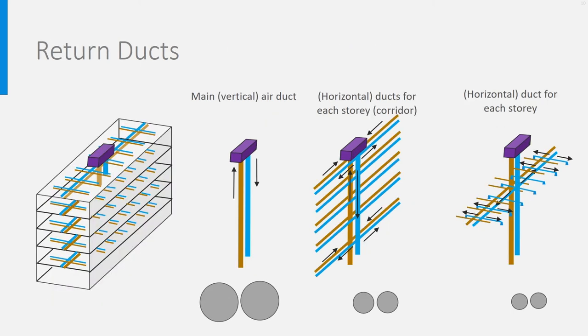This was all for the supply ducts. But when mechanical exhaust is applied, we also need return ducts, which have quite the same size as the supply ducts. So the total space needed is like on the picture. Additionally, sometimes, separate pipes are used for cooled air and for heated air, doubling again the amount of pipes. Cold and warm air are then mixed at room level. However, from the spatial and financial point of view, this is not very efficient.